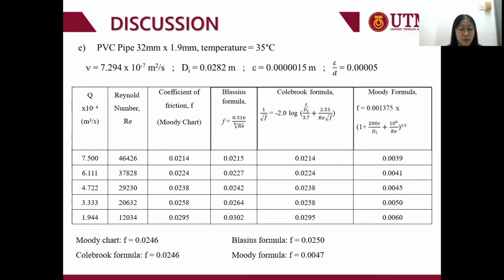Last is the PVC pipe with dimensions 32 mm × 1.9 mm. From the Moody chart, the coefficient of friction is 0.0246, the same as the Colebrook formula. The Blasius formula gives f = 0.0250, and the Moody formula gives 0.0047.